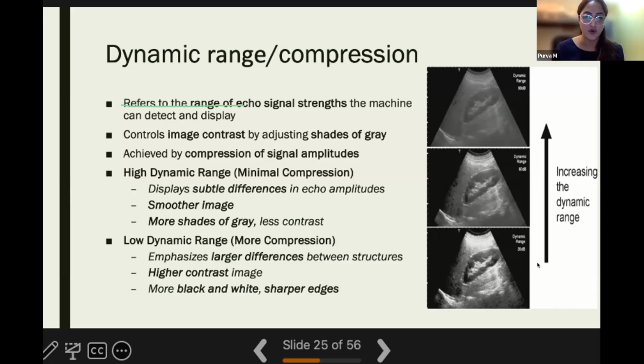If you see here, the bottom image shows you a very low dynamic range. You can see only white and black, and a very crisp image with very high contrast, kind of jarring to the eyes. The second one is optimal contrast. That is the optimal dynamic range we would go for. You would not miss any finding, but at the same time, the image does not look jarring to you. The third one is a very smooth image. It is important in diagnostic ultrasound to get such an image because you do not miss any of those gray speckles. But when it comes to needling, you can get away with probably the second image.